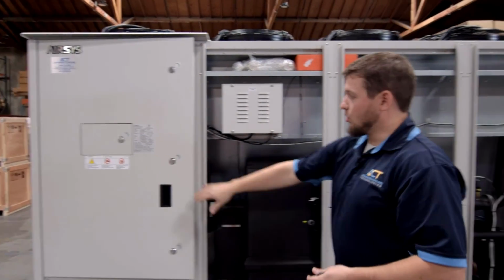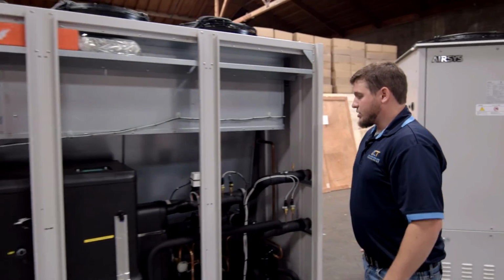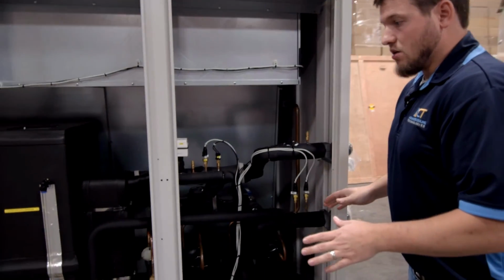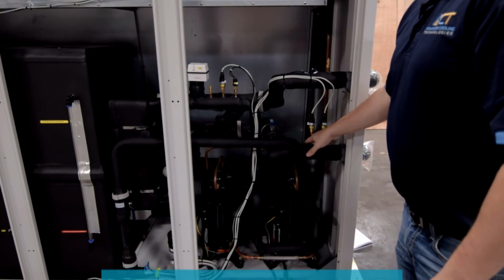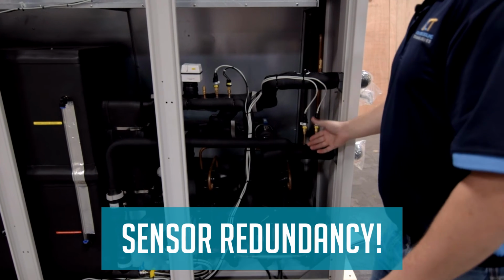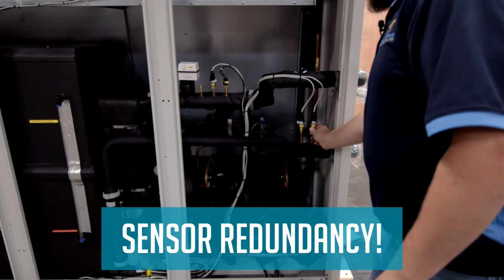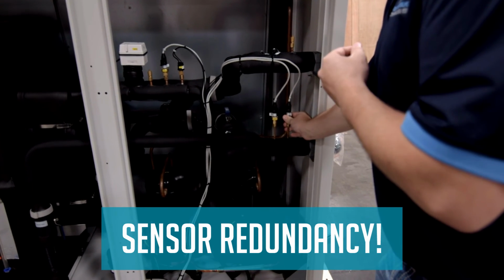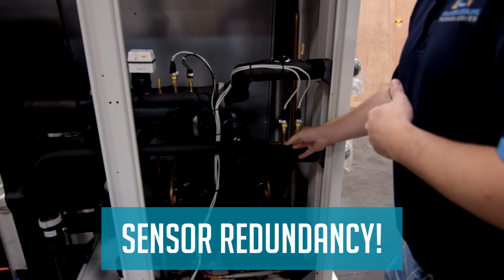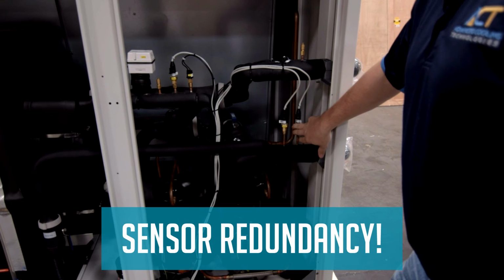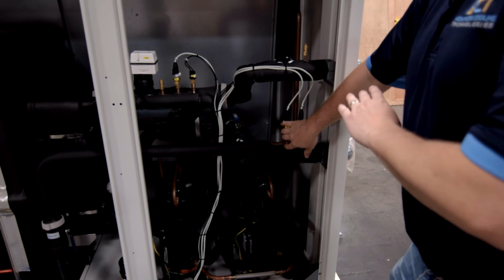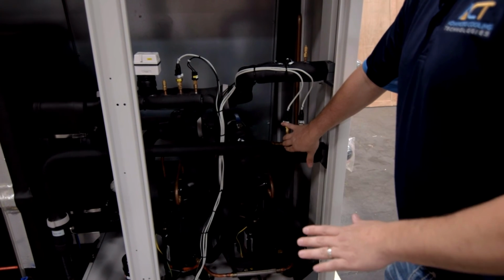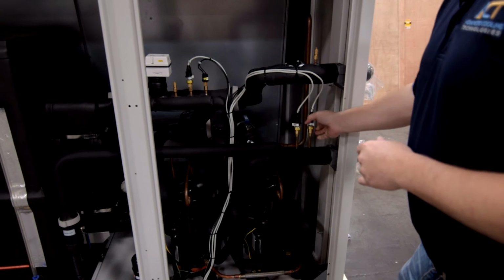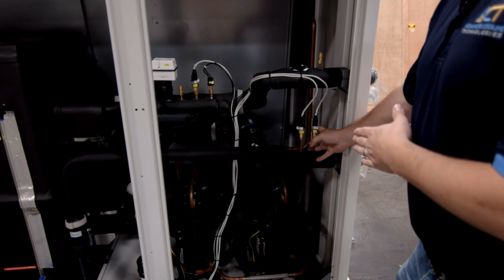On top of the main controllers being redundant, you can also see throughout all the systems in here that there is redundancy in the sensors. Something as simple as a sensor is something that we cannot take for granted. So that's why we have redundancy in all of our sensors. So if one sensor goes down, the other sensor can still operate the whole system and it doesn't require any kind of downtime. On top of that, we're able to determine if a sensor has failed, remotely detect that, and get a technician out there and resolve it before there's ever any sort of issues.